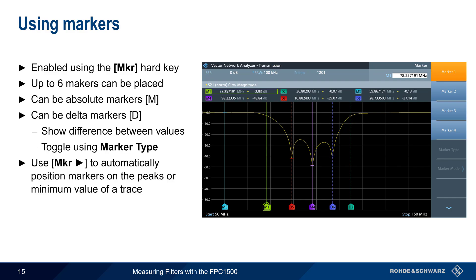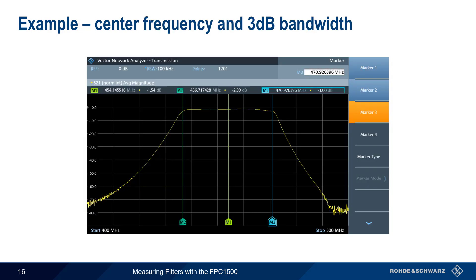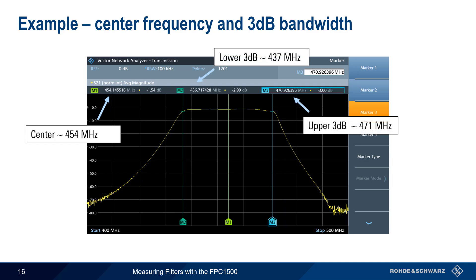Filter characteristics are determined using markers, which are enabled using the Marker hard key. Up to six markers can be placed on a trace, and these can be either absolute markers or delta markers, which show the difference between marker values. This can be toggled using the Marker Type key. Another Marker hard key is used to automatically place markers on the peak or minimum values of the displayed trace. We've placed three markers: one on the center frequency of our bandpass filter, here approximately 454 MHz, and one each on the lower and upper 3 dB points, which is how filter pass band is normally specified. Looking at the difference between these two 3 dB points, we can calculate the pass band as being approximately 34 MHz.